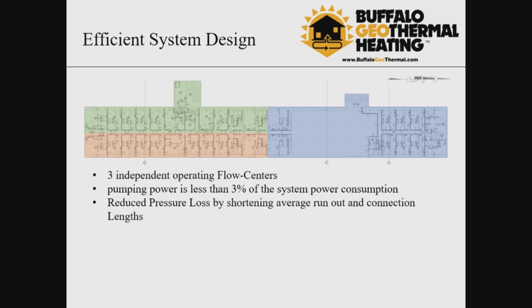The efficiency of a geothermal system is mainly determined by the heat pumps themselves, the fan power consumed, and then greatly also by the pumping power to supply each of these heat pumps with a source liquid. Speccing a heat pump with a high COP, ECM fans, wireless thermostats, that's all the easy part of the job. The real ingenuity comes in when we look at pumping power and how can we decrease it.